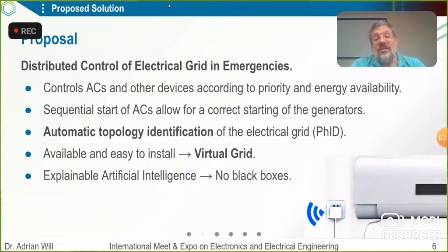Sequentially starting the ACs is a critical point. After a 2 or 3 hour blackout where the hospital didn't have energy—it has happened and will happen again—the hospital is hot, all the rooms are hot. So whenever your generator starts and you get power, all the air conditioners start at the same time and you get an outage again because the generator gets overwhelmed by the request of energy. So sequentially starting the air conditioners is necessary in order to not overcharge the generator. It's a critical point that the health department is asking from us.